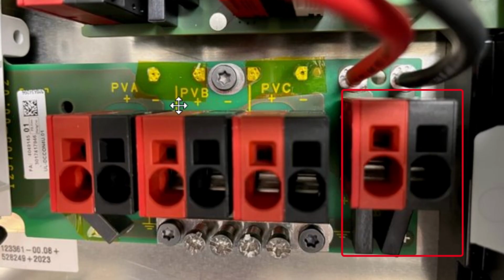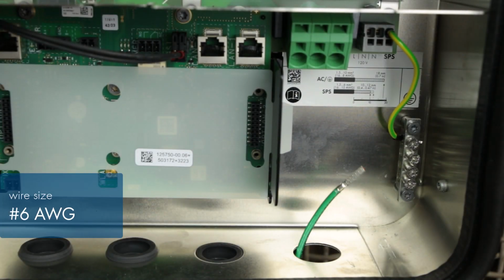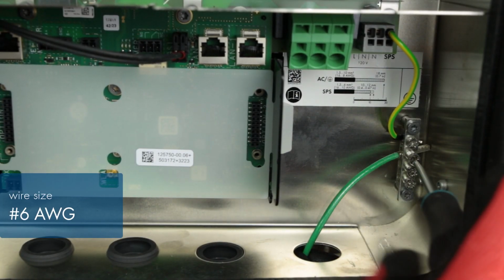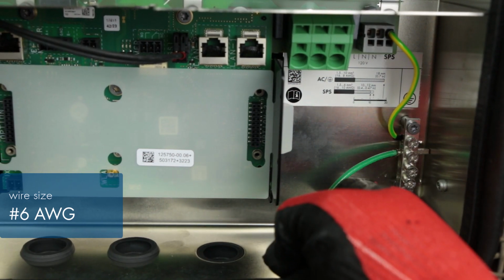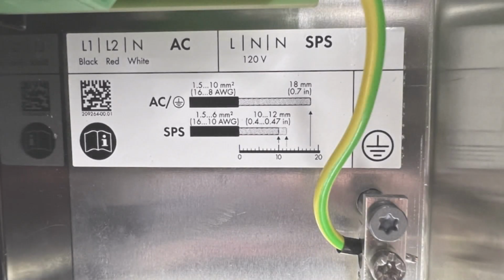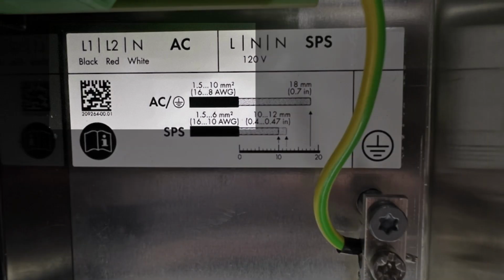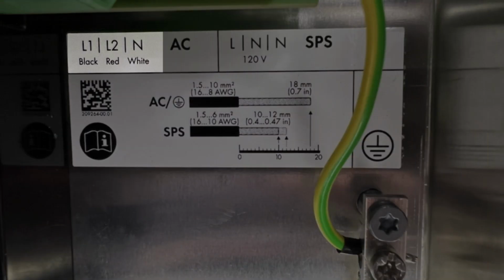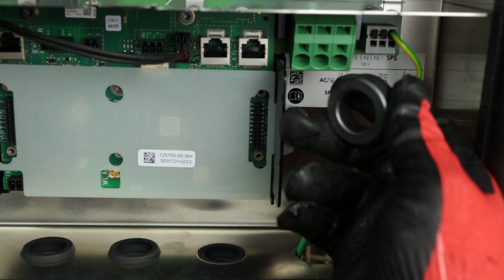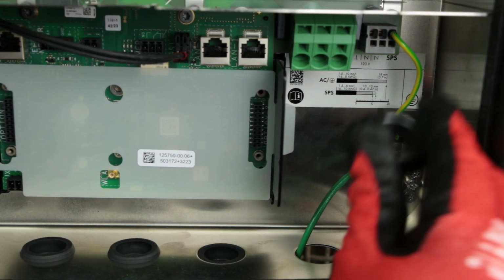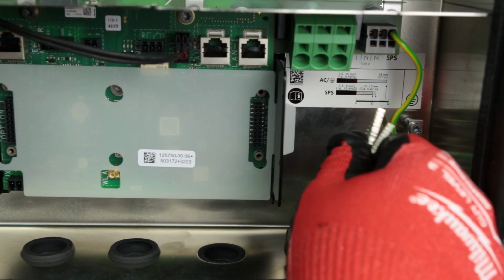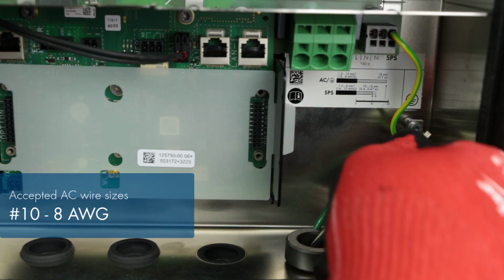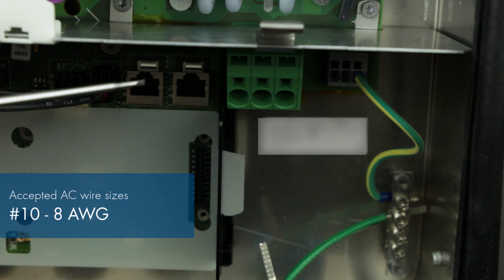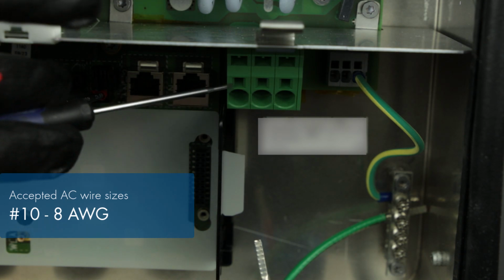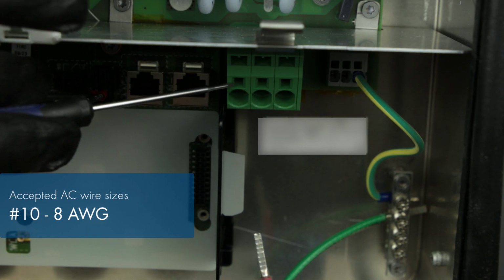For AC wiring, start with the ground cable, inserting it into the ground bus bar and tightening the bolt. Refer to the provided sticker for wiring L1, L2, and neutral wires. Lay the ferrite over the knockout and thread L1, L2, and the neutral conductor through the ferrite. Then, insert a flathead screwdriver to open the clamp and proceed to insert the wires to the respective terminals.